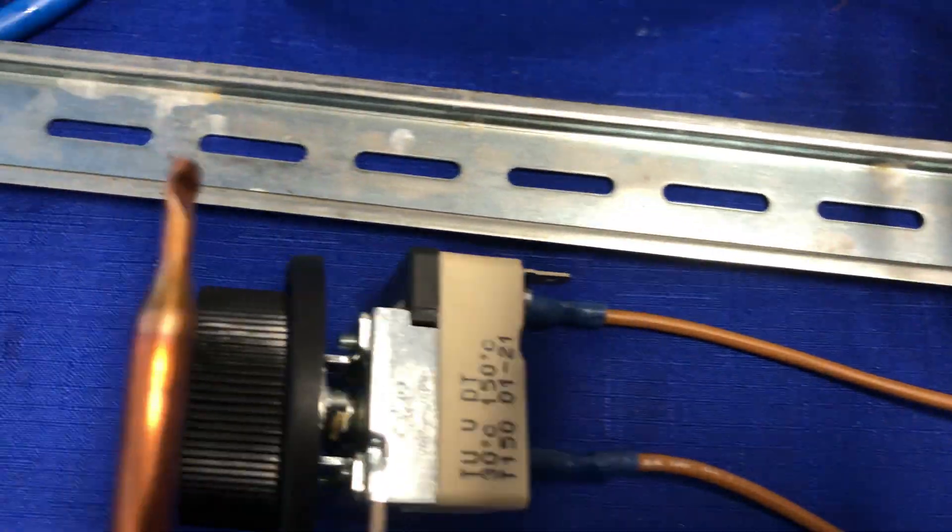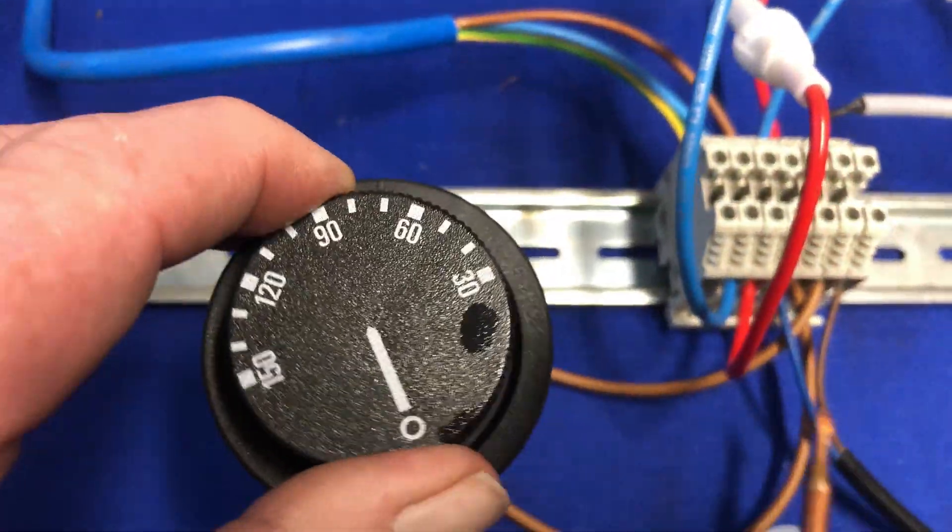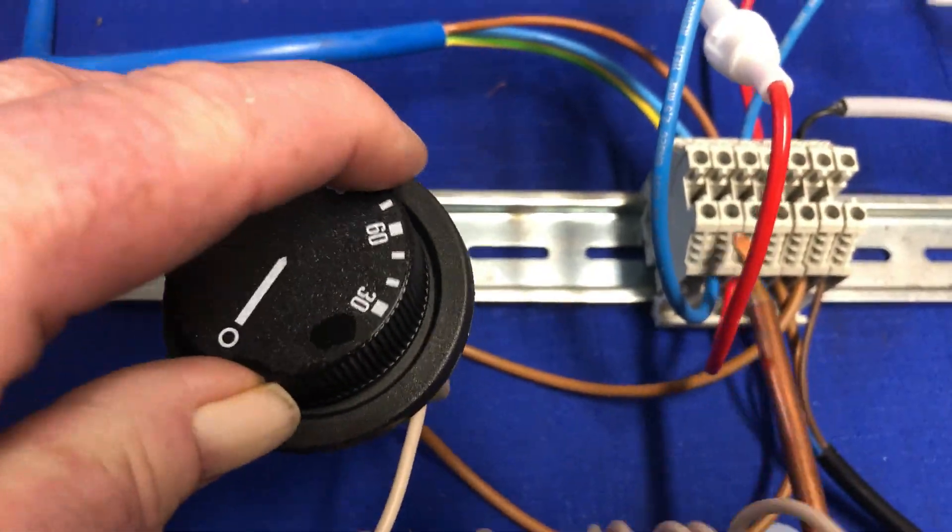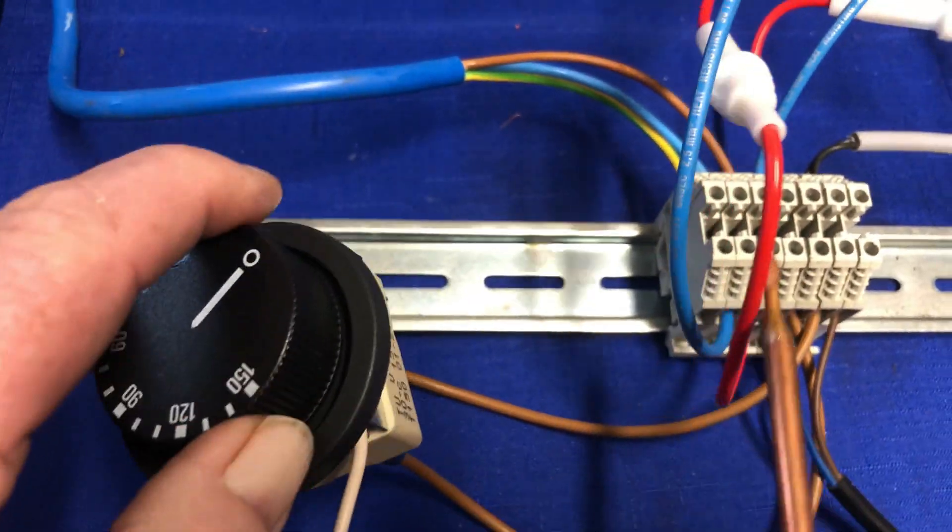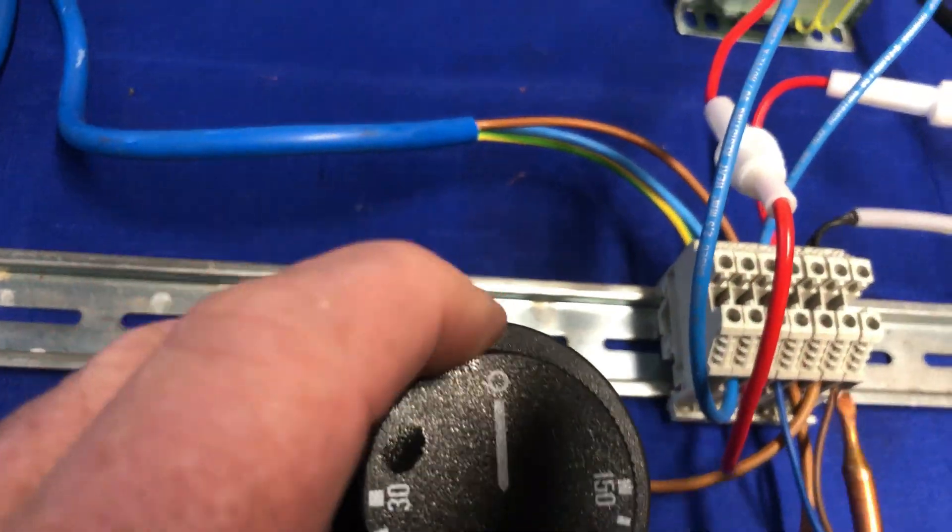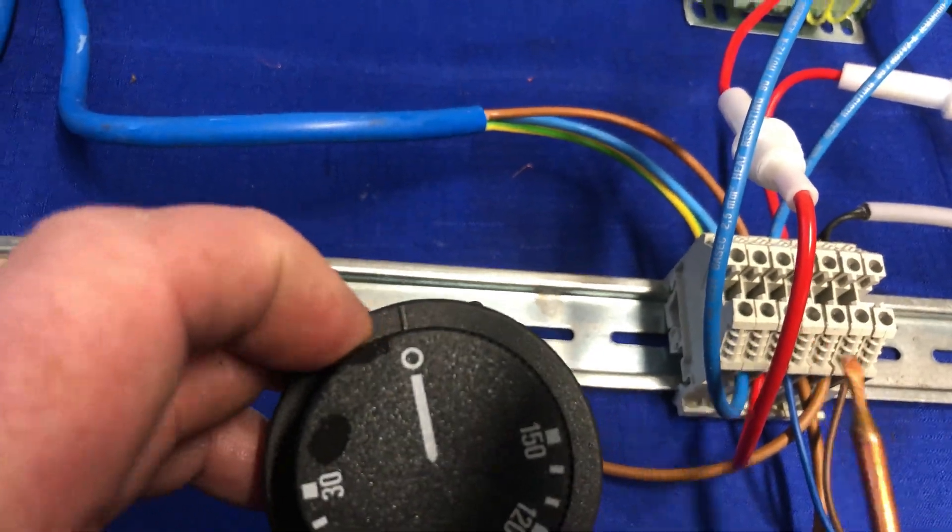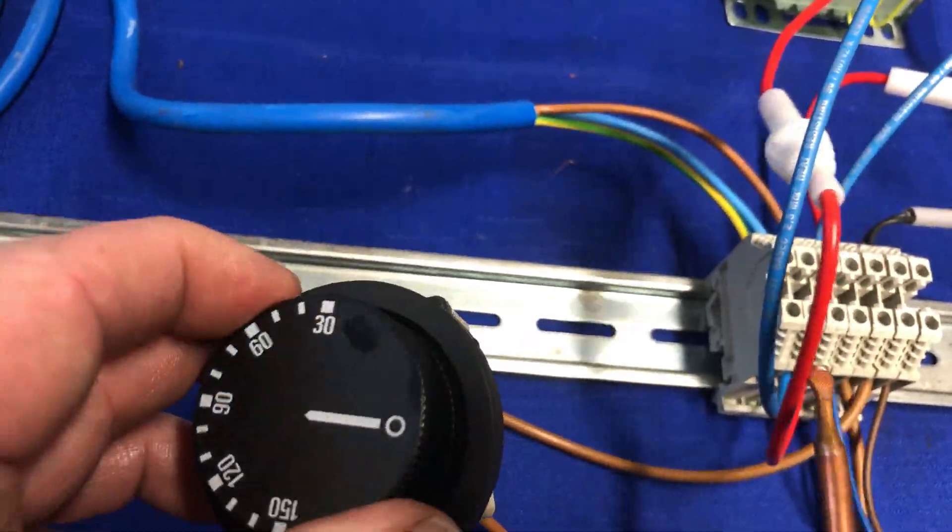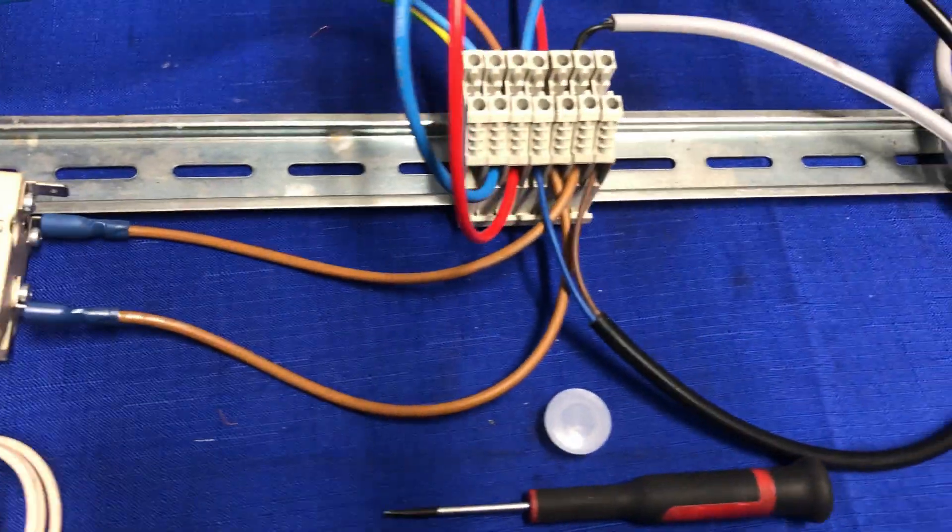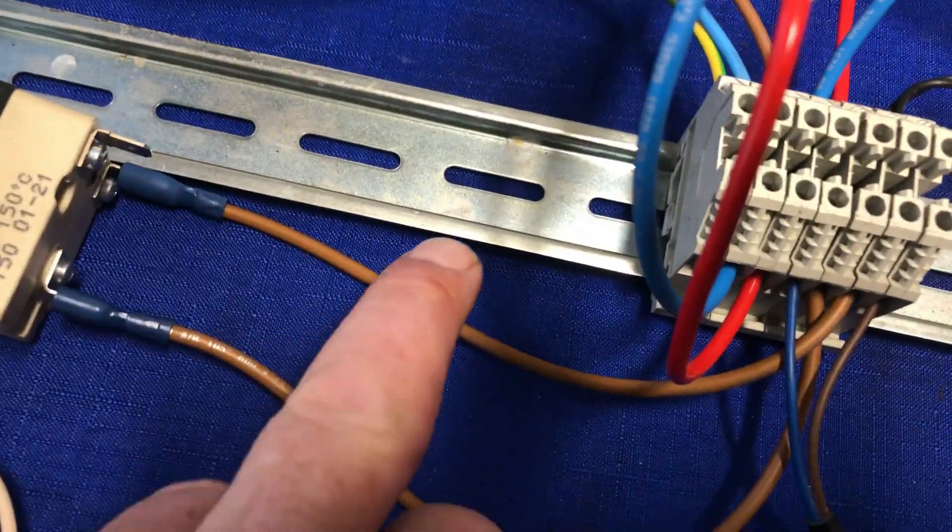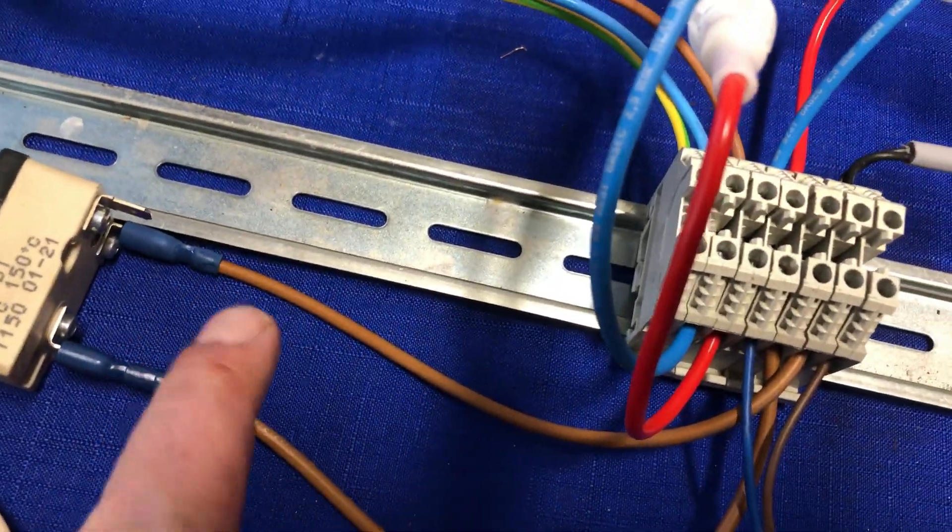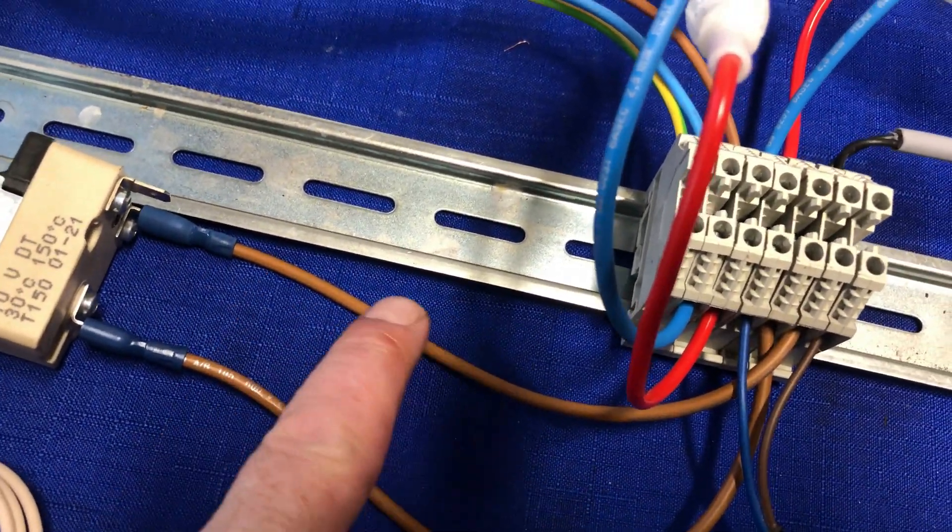The thermostat operates at whatever temperature you're working at. You'll see that's off - turn it on and you'll hear it click. We've got 24 volt coming into the circuit, 24 volt comes out, then it runs through the flow switch.